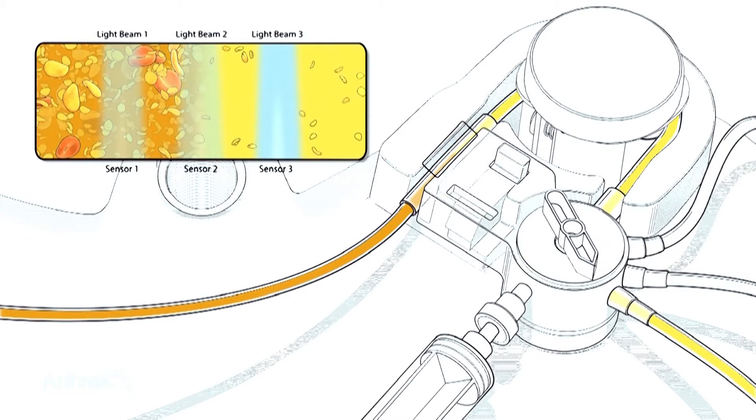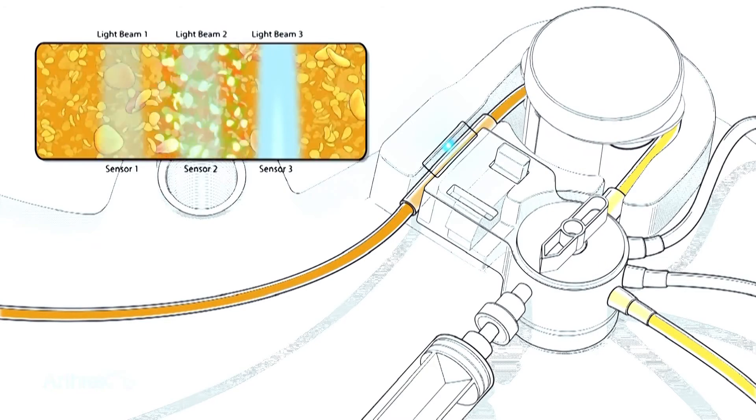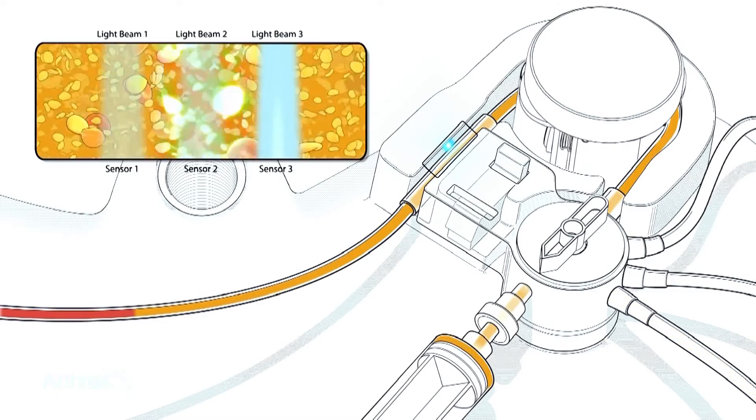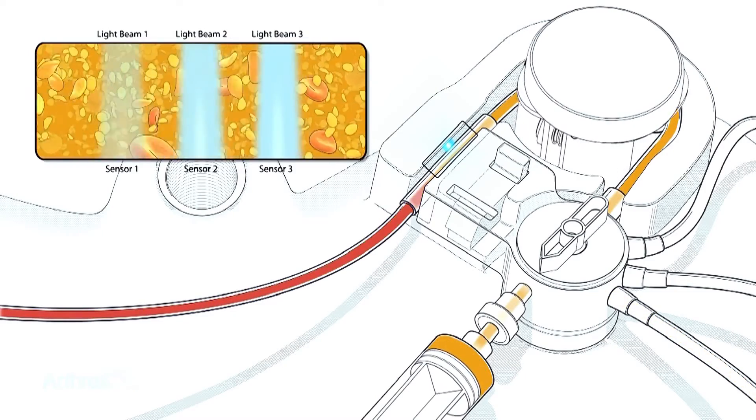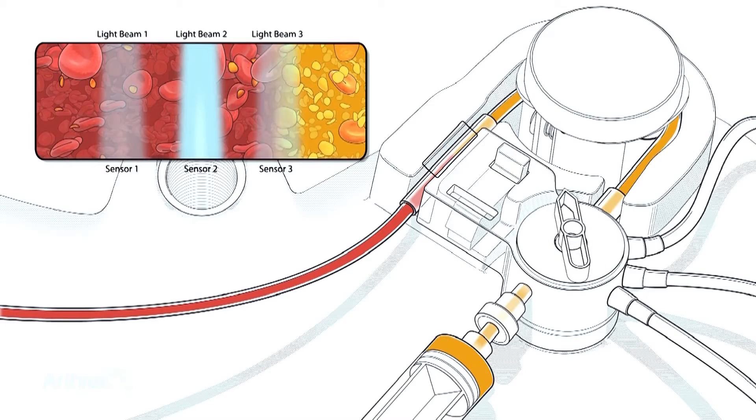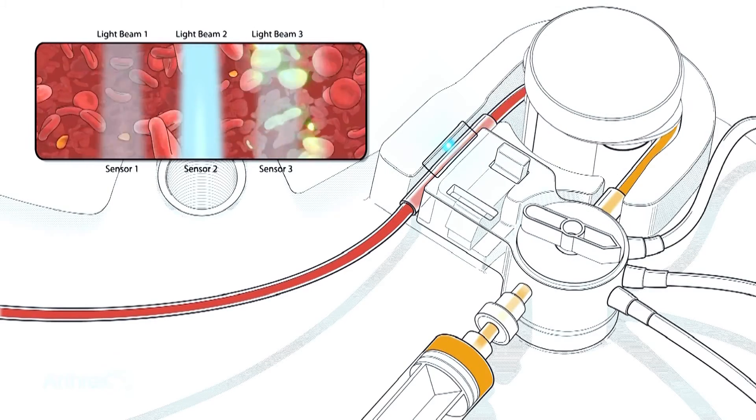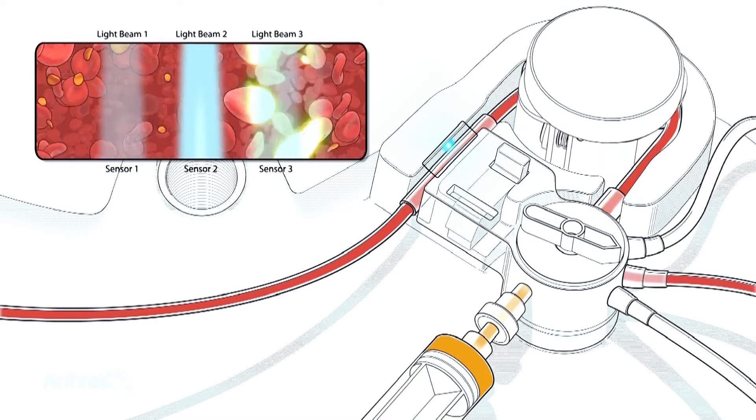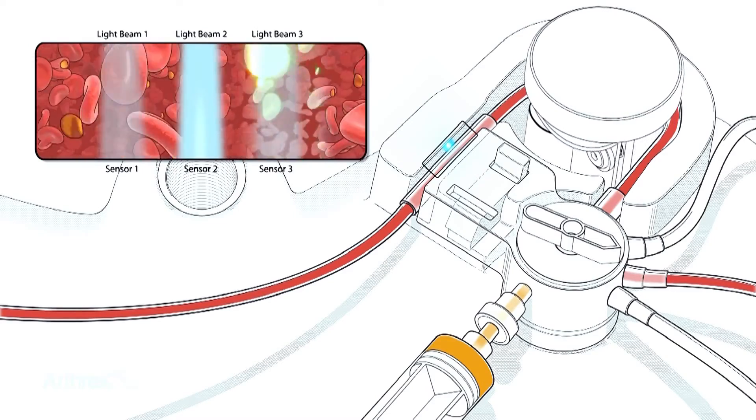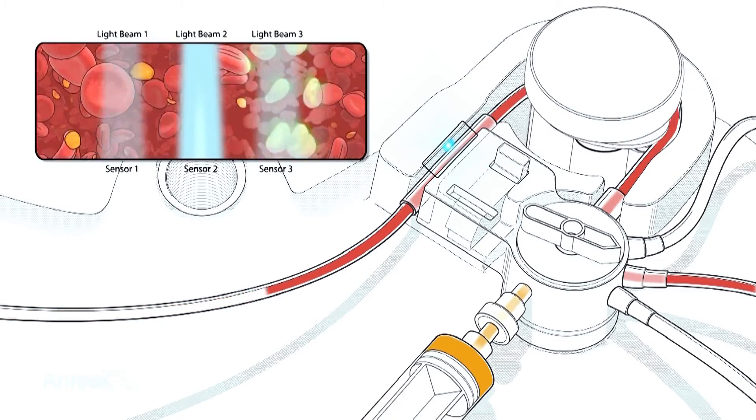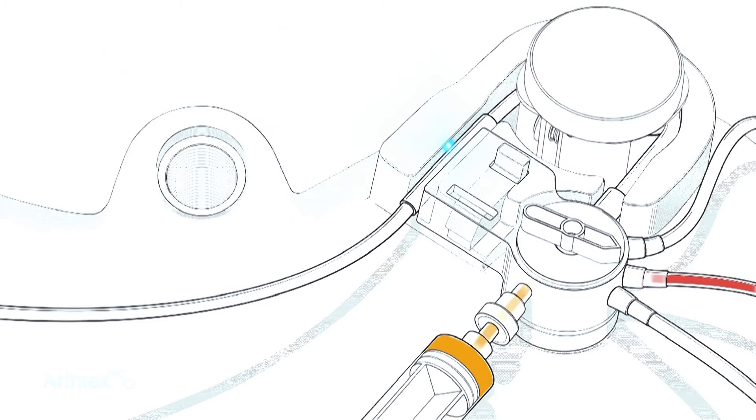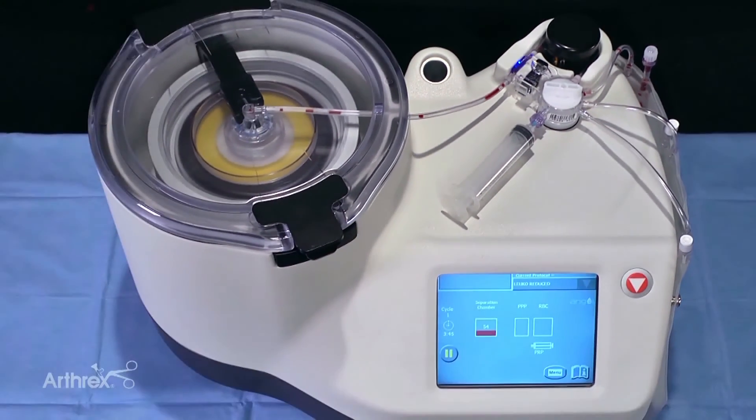Next is the platelet rich plasma. When the presence of platelets is detected by the 470 nanometer light beam, the valve is adjusted to direct the PRP into the collection syringe. PRP collection will continue until the 930 nanometer light beam detects red blood cells. Again, the Angel automatically adjusts the valve position to direct the red blood cells into the RBC out compartment.